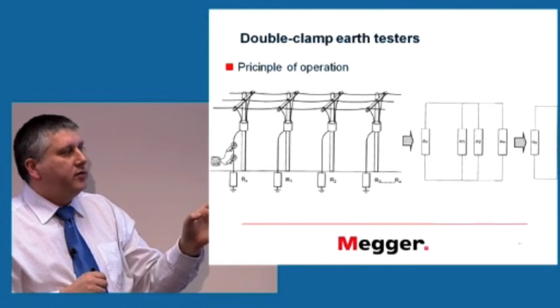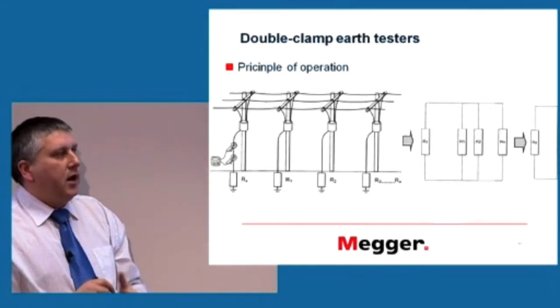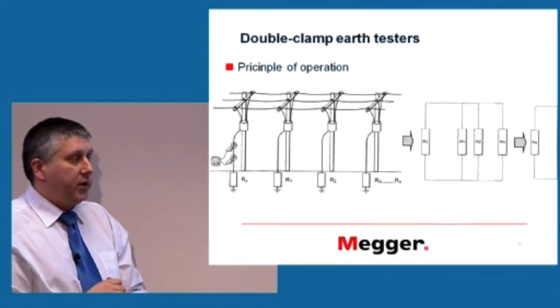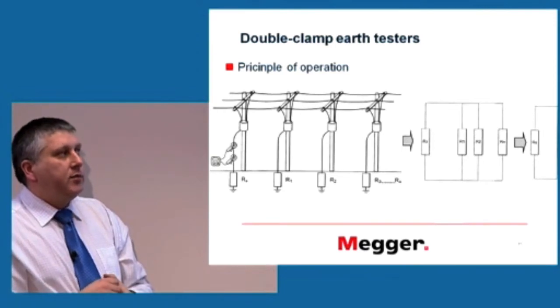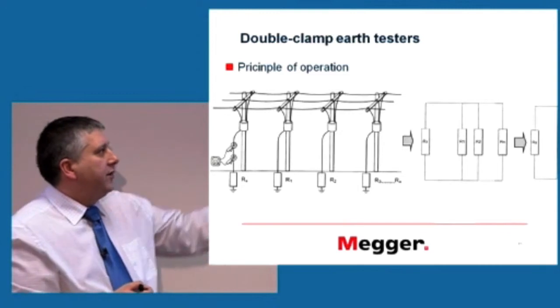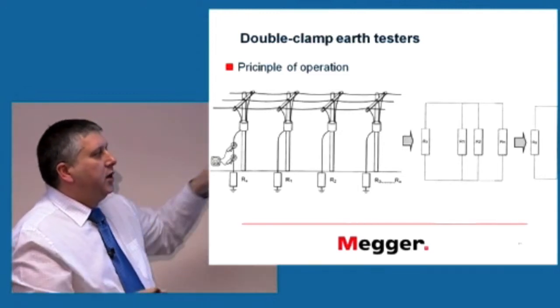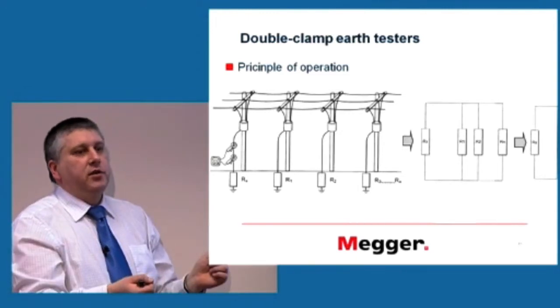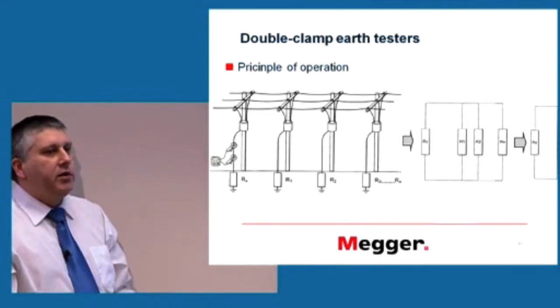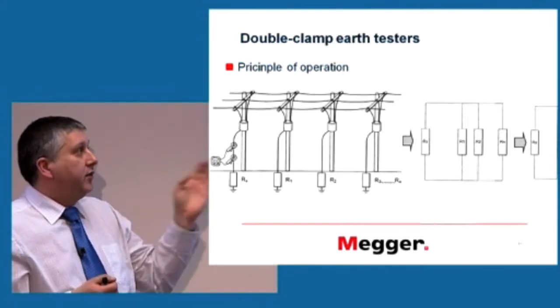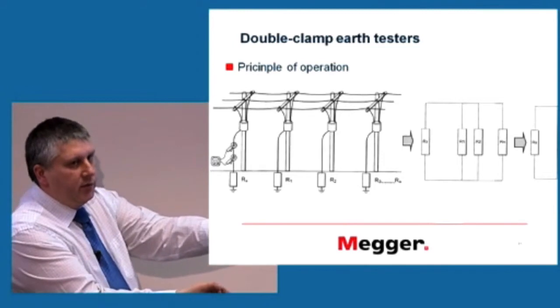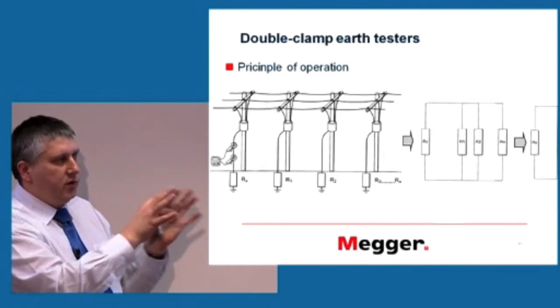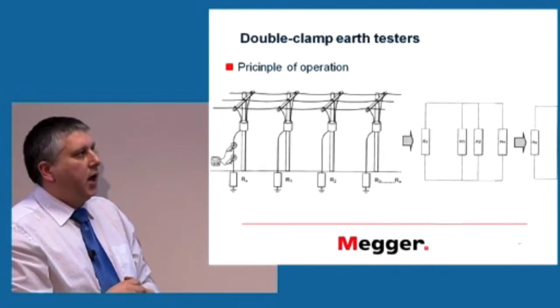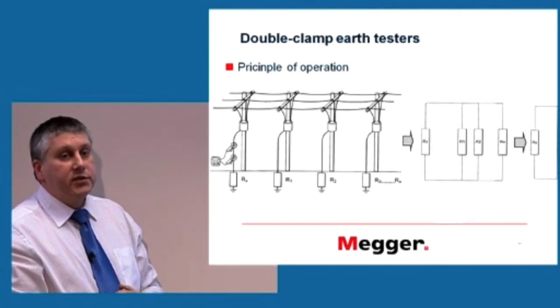Obviously, there's error involved because we are assuming that all the others are much lower than our primary electrode, but it can be shown that in real life it saves a lot of time. The other alternative is to break that connection, install an ohm meter and measure that value, which becomes very time consuming. With a device like this, we can just go there, clamp around it, and if we know that the rest of the system will conform to our assumption, we get a very quick answer.